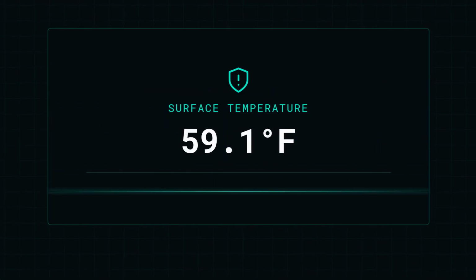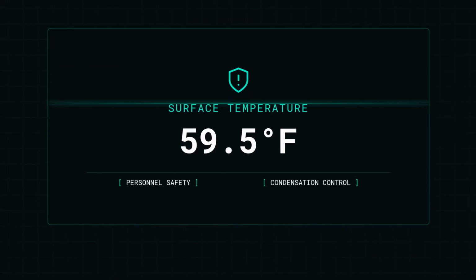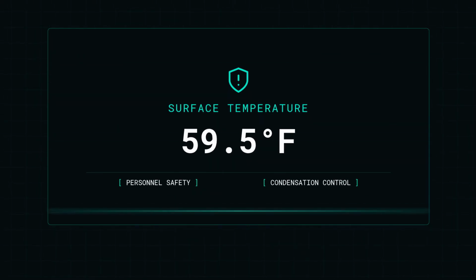The surface temperature is 59.5 degrees Fahrenheit. This is the temperature on the outside of the insulation, which is important for personnel safety and condensation concerns. These values help engineers properly size insulation systems and evaluate energy efficiency.